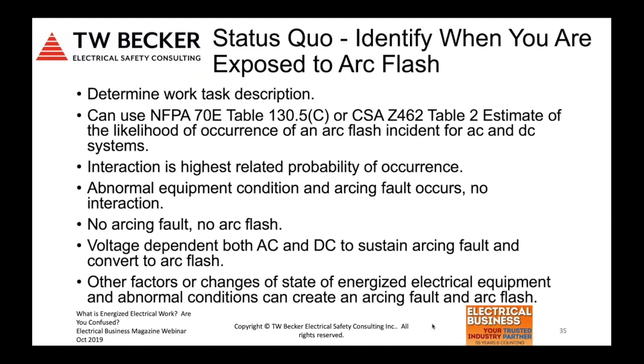So identify when you're exposed to arc flash. Again, a little more clarity here. I mentioned it just earlier, but determine the work task description again. We have the two new tables available in CSA Z462. So you need to do an arc flash risk assessment. I also wanted to say that the arc flash risk assessment in the latest editions is also a true risk assessment. We have to identify the hazards, assess the risk, and determine the hierarchy of risk control methods to apply against the risk to reduce the risk so the residual risk is as low as reasonably practicable.